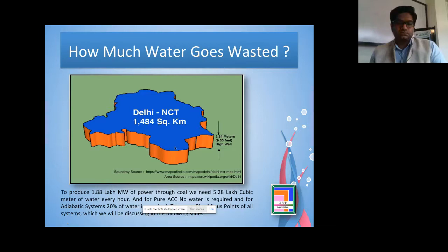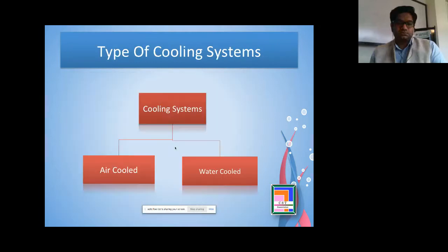And if we go for adiabatic technology, we only need 20% of this water, and this 20% of water can either be condensed from the atmosphere, or it can be used from municipality waste or any other source. So basically we will not require any kind of outside water to run these thermal power stations. So there are two types of cooling systems in a power plant. One is air cooled, another is water cooled.